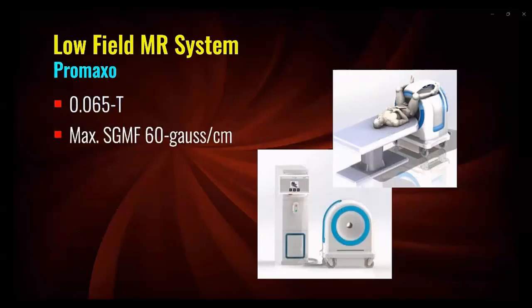The ProMaxo scanner has a unique single-sided configuration specially designed to permit urologists to perform MRI-guided prostate interventional procedures in an in-office setting. This is a portable MR system that is easily rolled into place so it can be set up for patient use within a matter of minutes. The ProMaxo scanner operates at a static magnetic field of 0.065 Tesla, and has a highest spatial gradient magnetic field of 60 Gauss per centimeter.